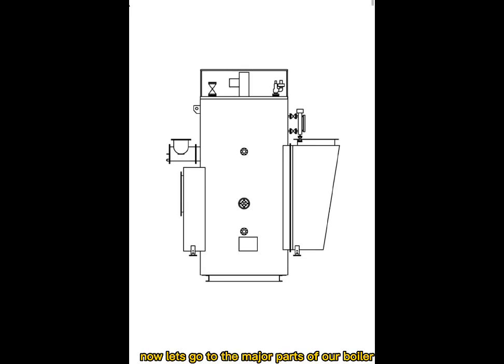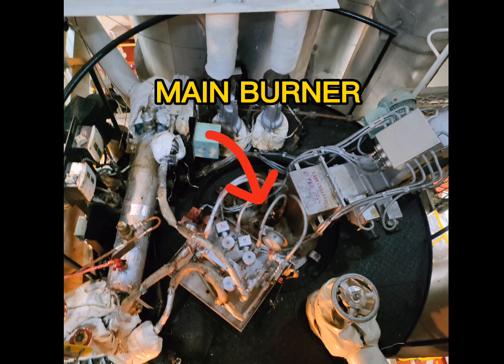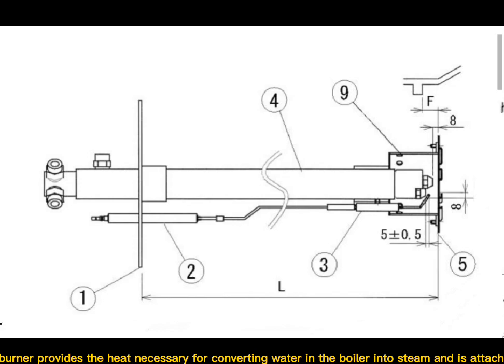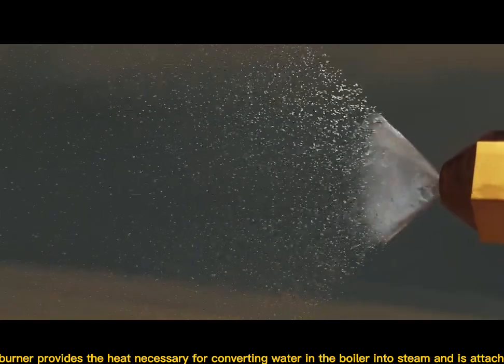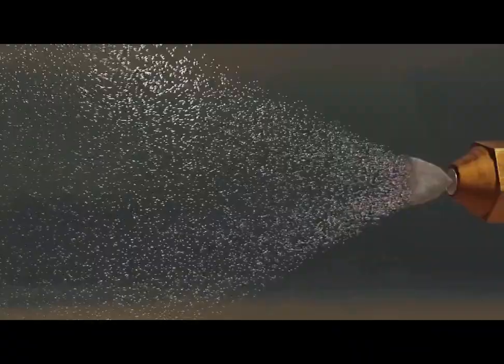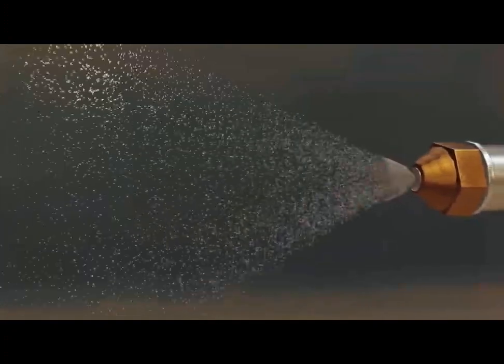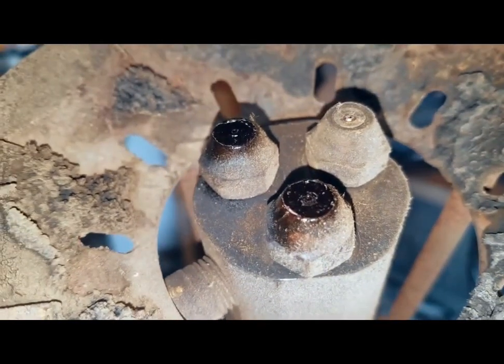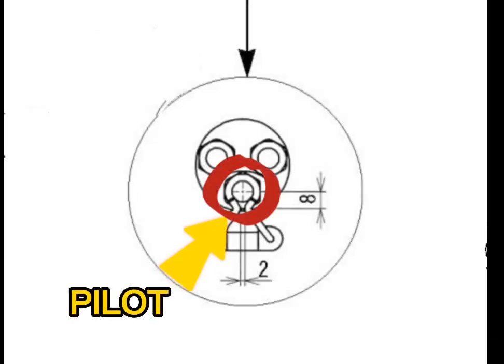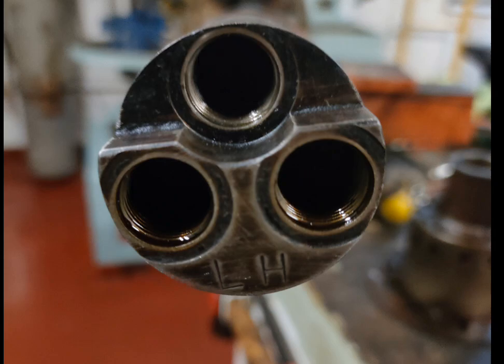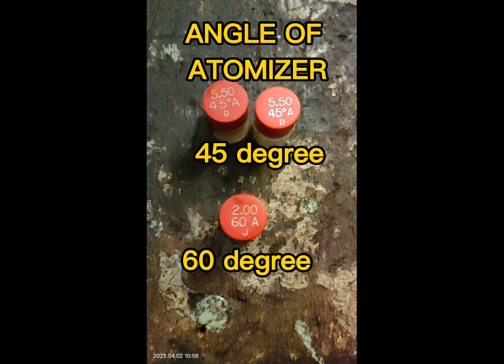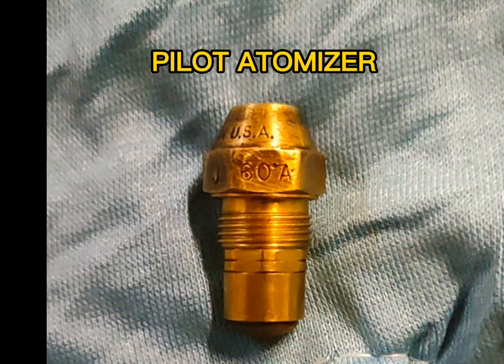Now let's go to the major parts of our boiler. Main burner: the boiler burner provides the heat necessary for converting water in the boiler into steam and is attached to the boiler. There are two types: pilot and main. The pilot burner is allotted a limited period of ignition during which it acts as a source of heat for the main burner, and once the time is over, the pilot flame goes off. A pilot burner consists of a detachable nozzle with five holes to atomize the diesel fuel for instant ignition.